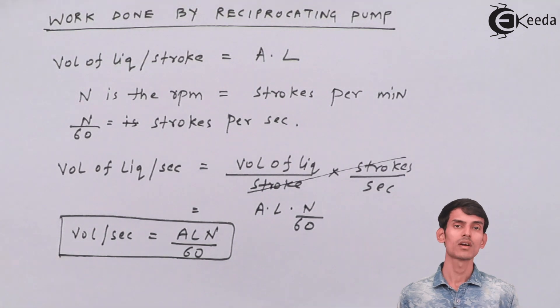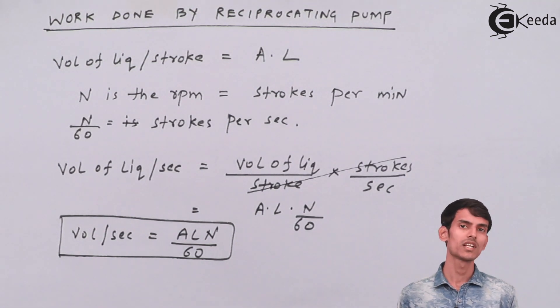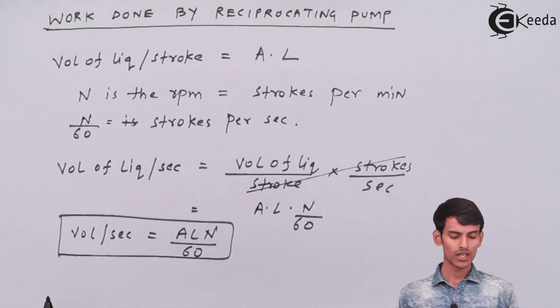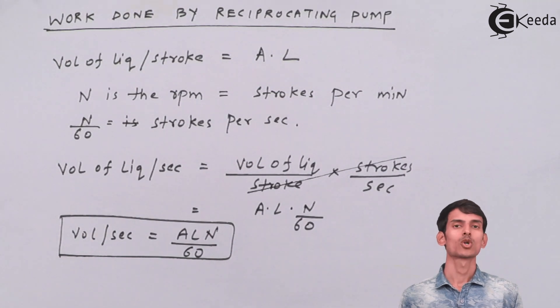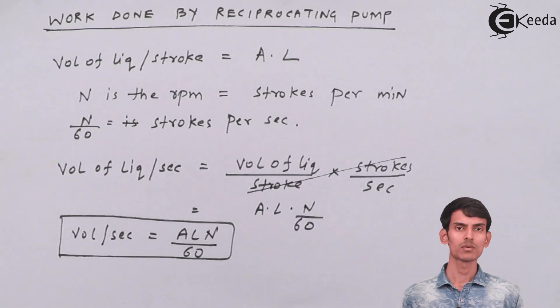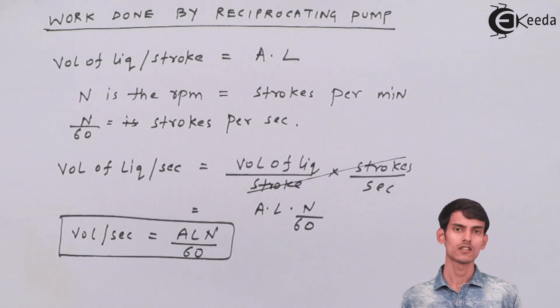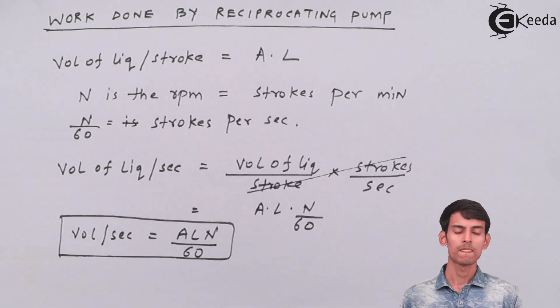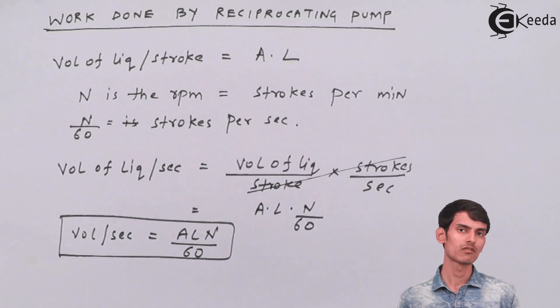So the volume of liquid delivered per second is A × L × N/60, where A is the cross-sectional area of the piston, L is the stroke length, and N is the RPM. This gives you the volume delivered per second.